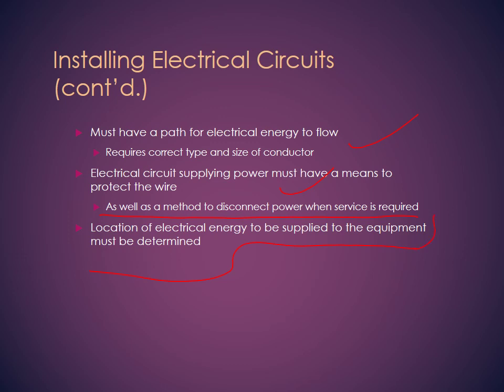Location for the disconnect switch. As a general rule, you want the disconnect switch to be within reach of the equipment, in case something goes wrong, so you can reach out and unplug it. And it's good to have 2 ways to disconnect the power from the equipment: a regular switch and a big major disconnect switch that shuts off the power to the equipment, and also all the switches around it and the control as well.